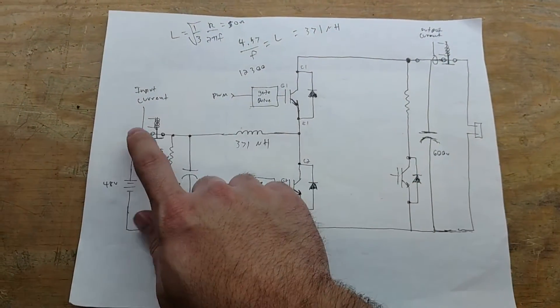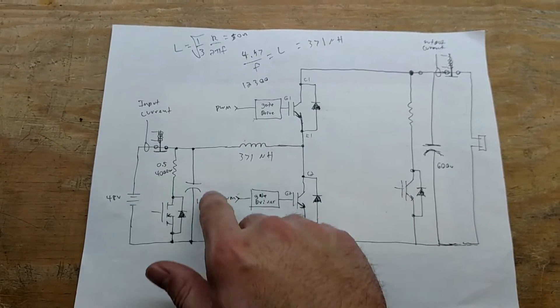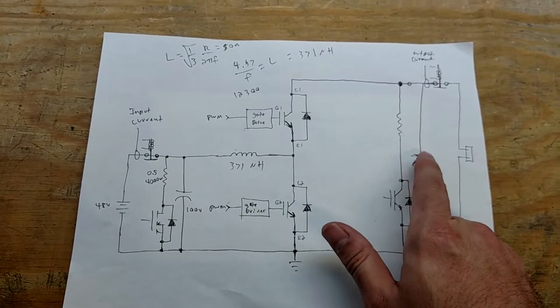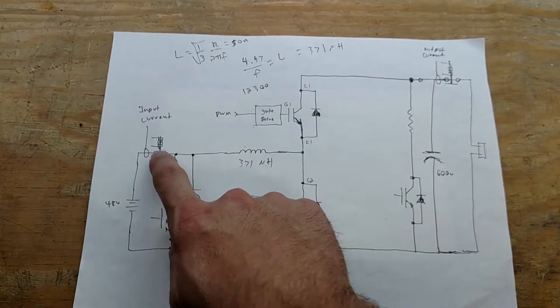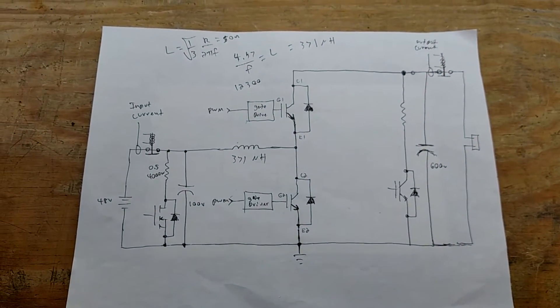For these contactors, if we close them, we're going to charge up these big caps and we'd have a bunch of inrush current. We could weld the contacts on the contactors. So what we need to do is pre-charge.